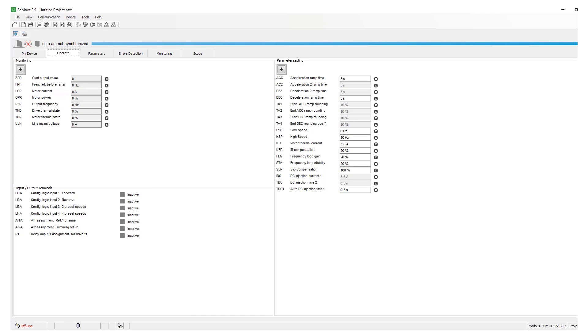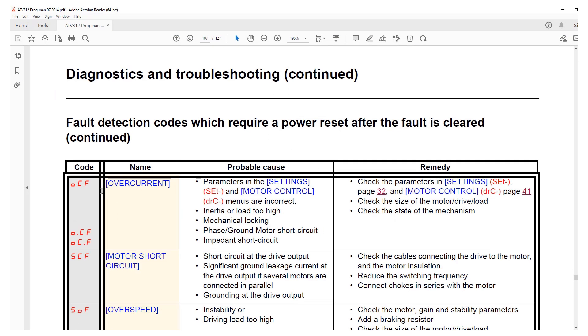The last thing is to look at the fault itself and confirm if it is OCF, O.CF, or OC.F. If it is OCF then we already talked about the things to check. If it is O.CF it could be a phase short circuit.